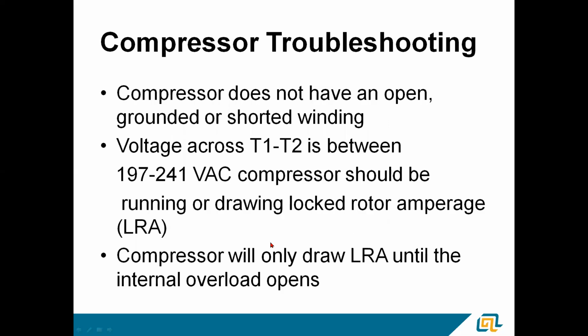So here's what we know so far. Compressor doesn't have an open, grounded, or shorted winding. We checked that. We ohmed out the compressor. We were comfortable there. Voltage across T1 and T2 is between 197 and 240 volts. The compressor should be running or drawing locked rotor amperage. Something should be happening. If you've got voltage there, you should have an amp clamp on there when it's trying to start. You should see amp draw on that. It will only draw locked rotor amperage until the internal overload opens.